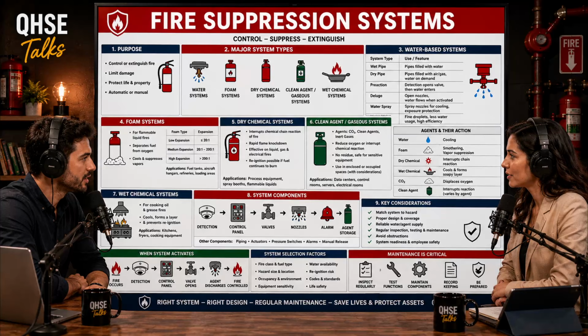Like chemically? Yeah. Burning magnesium, for example, burns at over 5,000 degrees Fahrenheit. It is so intensely hot that it will literally rip the oxygen atoms right out of the H2O water molecules to fuel its own combustion. It uses the water as an oxygen source. That's terrifying. It is. And when it strips the oxygen from H2O, what is left? Hydrogen gas. Which is highly explosive. Exactly. So by putting water on a magnesium fire, you're feeding it oxygen and simultaneously generating a massive cloud of explosive hydrogen gas. That sounds like a complete nightmare for a safety engineer.